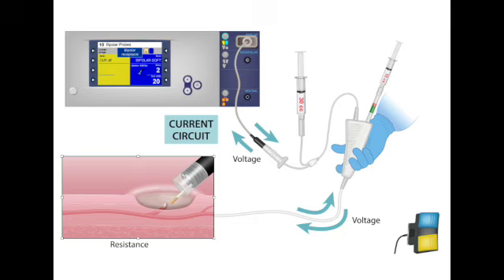The idea is the pressure should make the two walls of the blood vessel physically touch, make them kiss each other and occlude. Okay, so you're literally pinching the vessel closed with the probe tip first. Precisely. It's a mechanical stopgap initially, pure mechanics. So the flow is stopped mechanically. Then what? Then, and only after you've got that occlusion, that kissing happening, you apply the bipolar electrical current.